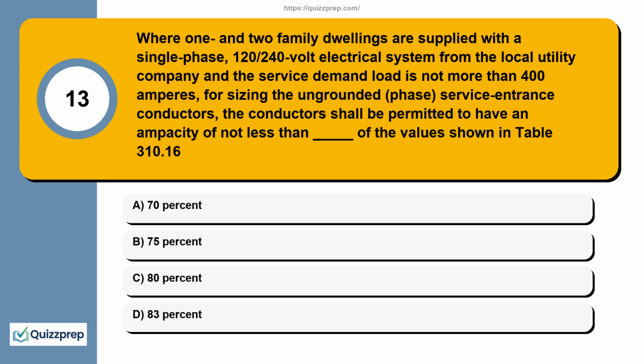Question 13. Where 1 and 2 family dwellings are supplied with a single-phase, 120/240-volt electrical system from the local utility company and the service demand load is not more than 400 amperes, for sizing the ungrounded, phase, service entrance conductors, the conductors shall be permitted to have an ampacity of not less than __________ of the values shown in Table 310.16. 70%, 75%, 80%, 83%.